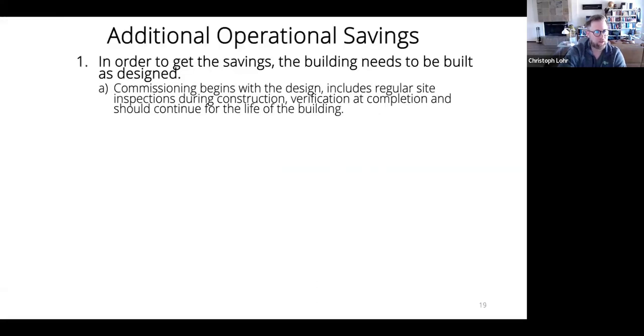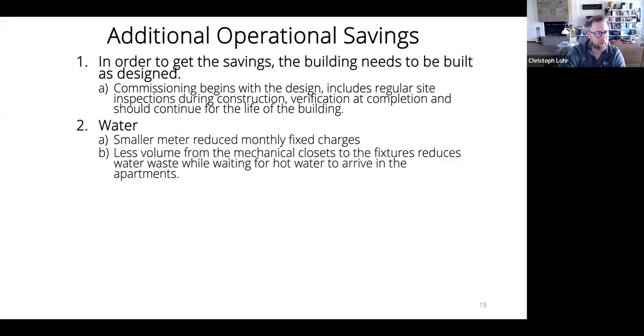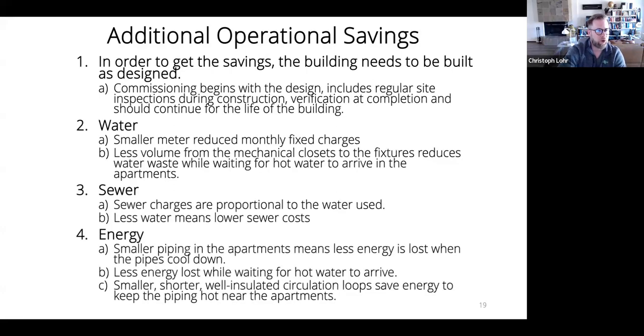Now, additional operational savings: in order to get the savings, the building needs to be built as designed. And so the commissioning begins with the design and includes inspections during construction. Gary, if you want to just put out the whole list on the chart there. So when you go through that, the water savings: a smaller meter reduces monthly fixed charges. You get more accurate readings of how much water you're using. Larger meters are notoriously inaccurate at smaller flows. So having a smaller meter will capture those smaller flows more, which may be able to prevent leaks.